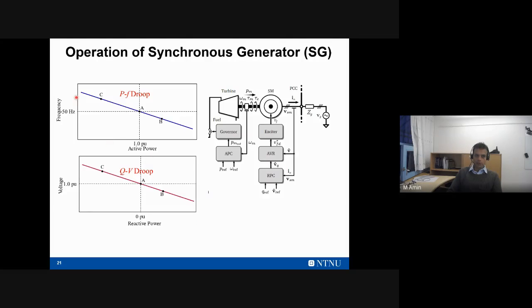We have this relationship between power and frequency. If a synchronous generator operates somewhere here and the load increases, then the frequency decreases. It has three levels of control: primary, secondary, and tertiary. The primary control acts instantly when there is a change in the voltage and the frequency. So it acts based on the power-frequency relationship. We have the power-frequency relationship installed here, and the voltage-reactive power relationship. So it always regulates the voltage and frequency at its terminal in the system. So they operate as expected.